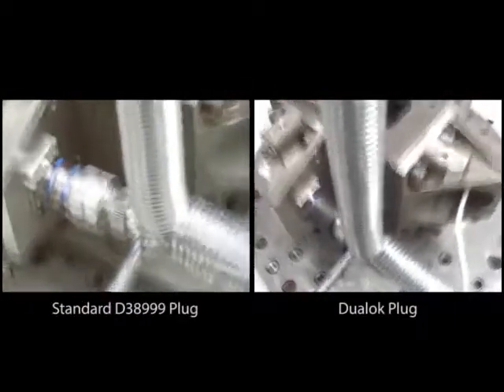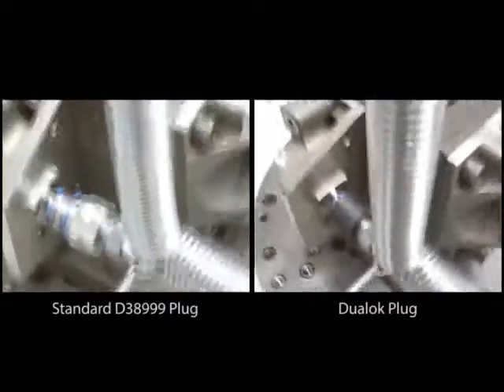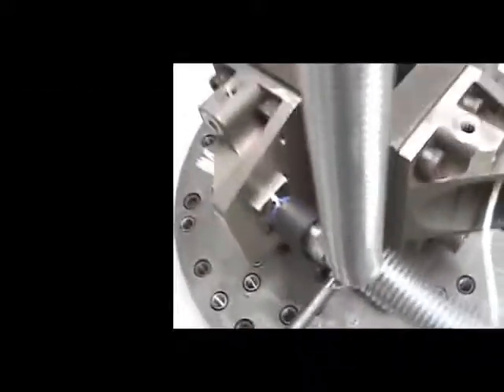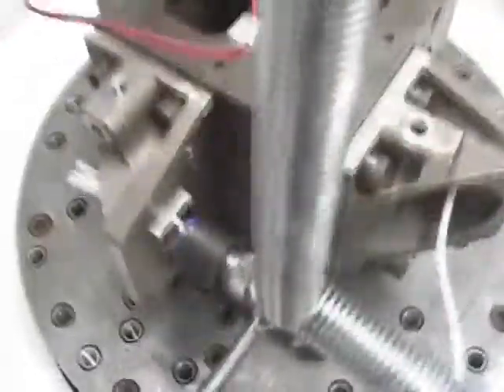The standard D38999 plug connectors came completely unmated after only 7 minutes. Dualok plug connectors not only didn't break loose, they didn't back off at all, as seen by the match marks.